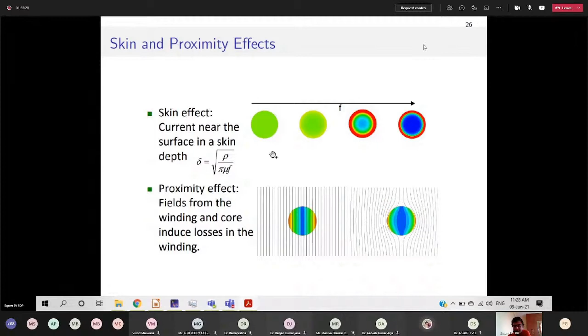Right. So what we need to decide is, as this number is going up, we need to optimize this. If frequency we don't have any control, for example, usually that is the case, then you have to go as low diameter as possible so that you get the full skin depth. So I think this Litz wire are a good option for this. Right, yeah. But Litz wires are expensive. So instead of Litz wire, you may go with normal wires, which you can parallel more, if that works. So using lower diameter and multiple wires of low diameter.